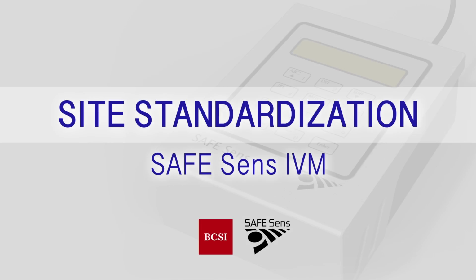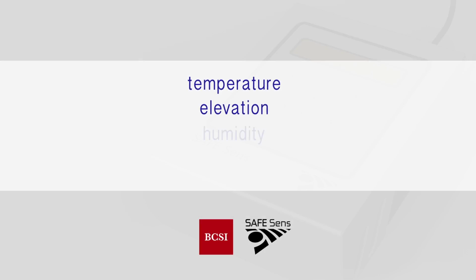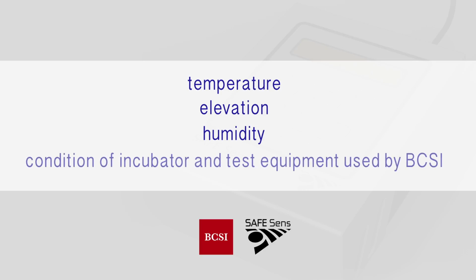Today we are going to perform the site standardization protocol for the SAFE Sens IVM. When the SAFE Sens system is adjusted at the factory, several environmental issues are in play: temperature, elevation, humidity, as well as the condition of the incubator and test equipment used by BCSI.